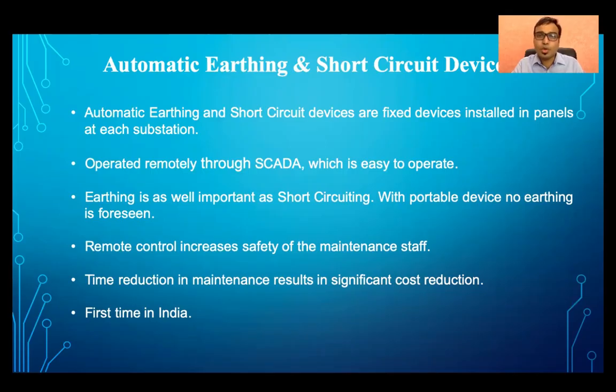In a portable device, no earthing is foreseen, while in the case of an automatic earthing device, we can do earthing also. Since it is a remote control device, it increases the safety of the maintenance staff. And with an automatic earthing device, the staff need not carry the bulky portable short circuit device. So it reduces the maintenance time, which results in significant O&M cost savings. This type of automatic earthing device we are using in Kanpur Metro is the first time in India for any DC traction system.